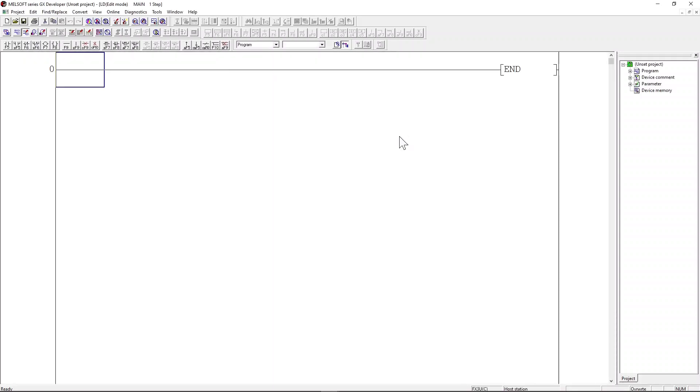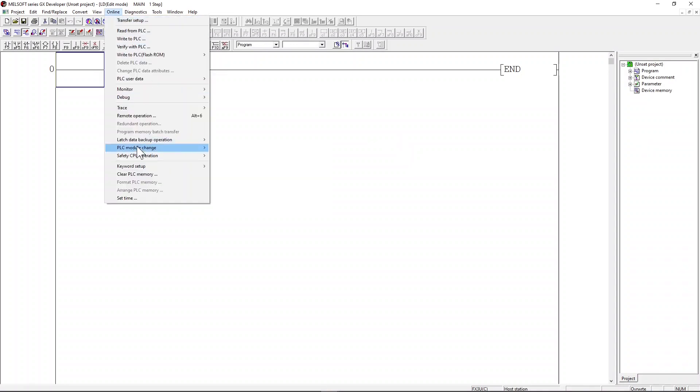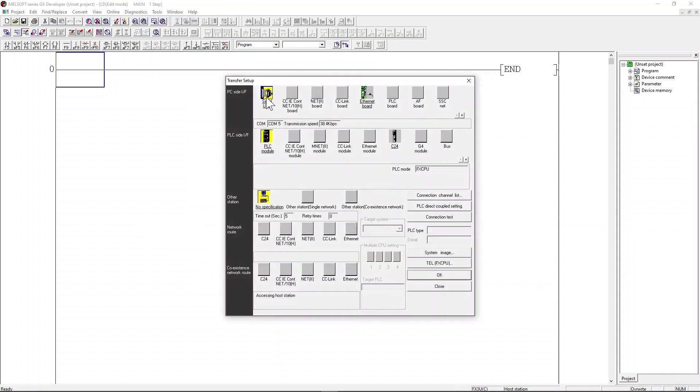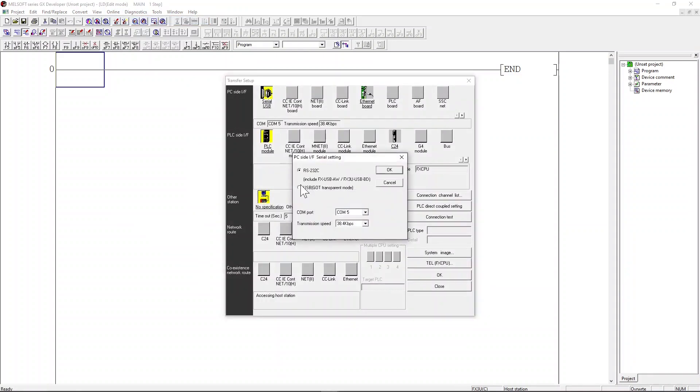We need to make sure the GX developer software can communicate with PLC through the serial port. Click on online and then click transfer setup. Next, click on the serial USB button. Make sure you choose the right COM port. On my PC, it is connecting through COM 5. Choose transmission speed of 38.4K BPS, then click OK.